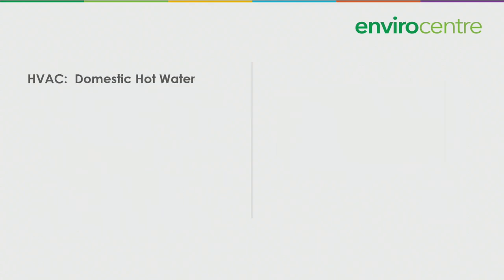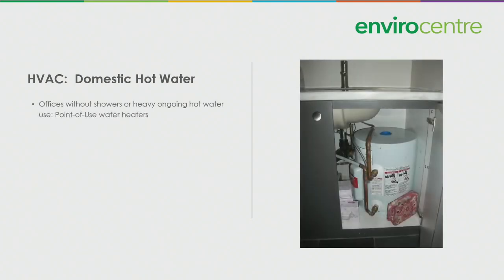On the domestic hot water front, what we see in the picture here is a point of use water heater. If you have an office that does not have showers, I would advocate using these because they will reduce the amount of water use, because you only have to run the water for a second before you get your hot water, rather than taking it from a central water heater where you're going to have to run the water for a while before you get it. You might be running it for minutes.